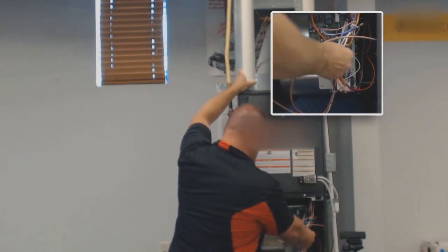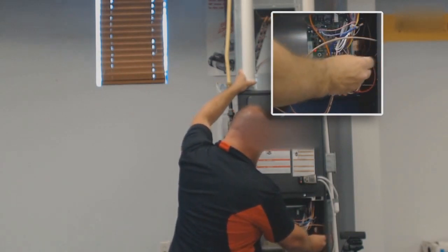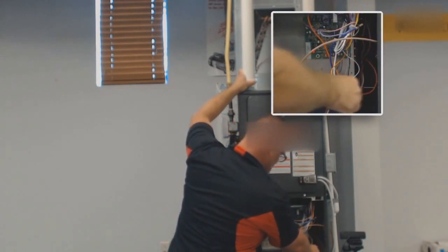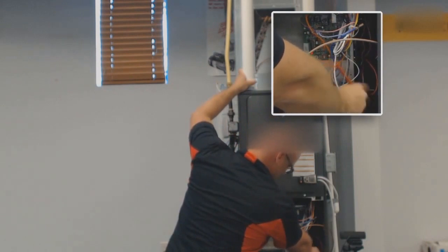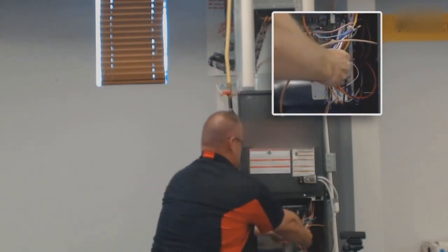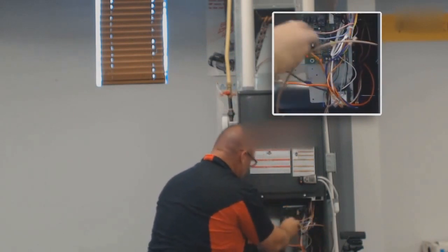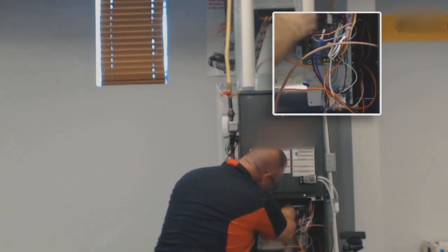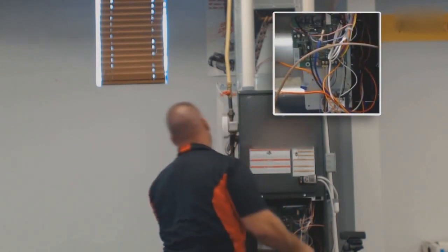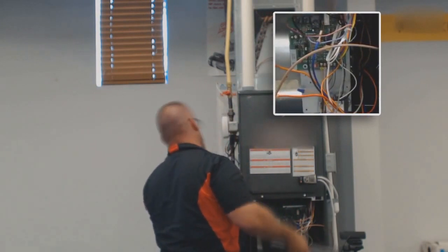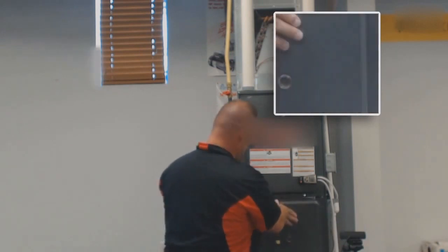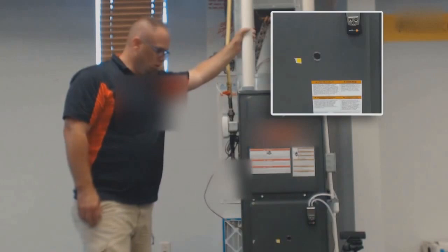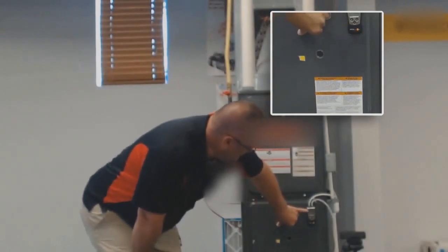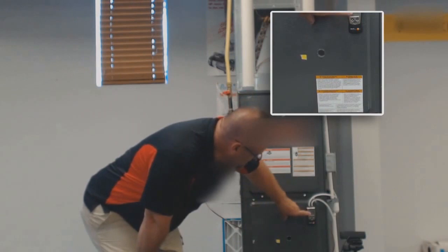Once it kicks off, we're going to go right back up to that high speed that traditionally is where a lot of us have these already set up. I'm going to go ahead and take it off that medium low, which is where we know now that it's supposed to be set up. Okay, so now we have our fan back on. With our fan back on, we can see that high speed has jumped this all the way up to just over 0.6, 0.63, 0.62, somewhere around in there.